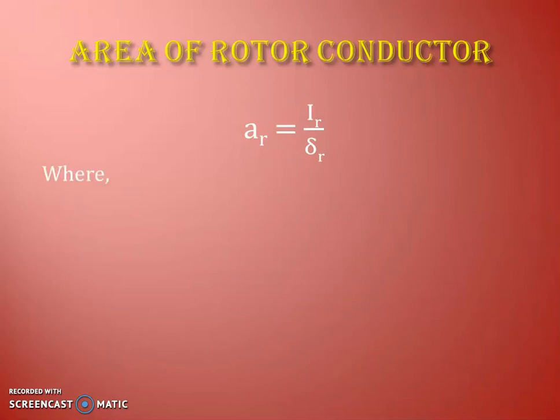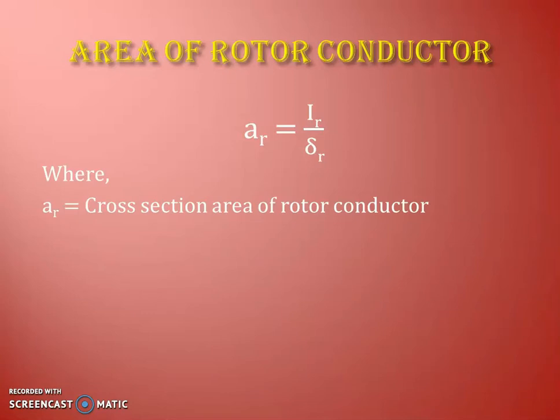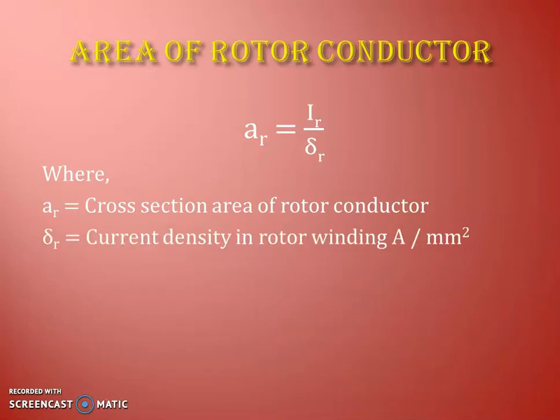AR is the cross-sectional area of the rotor conductor and delta R is the current density in the rotor winding in amperes per millimeter square. To avoid excessive rotor copper loss, we choose the current density in the rotor almost equivalent to the stator current density. We use a round type conductor for smaller motors and a bar type conductor for larger motors.